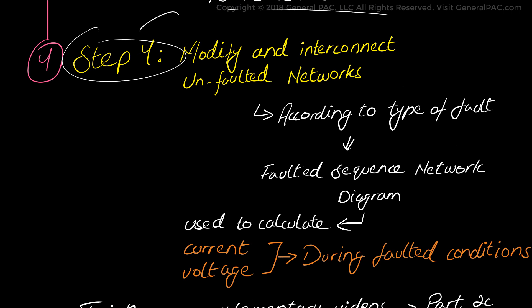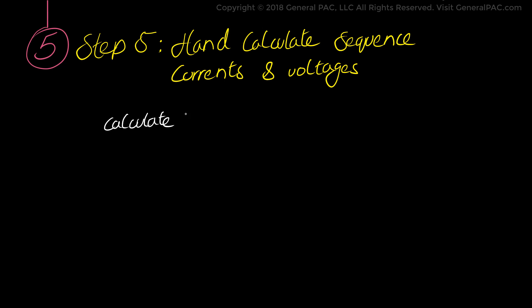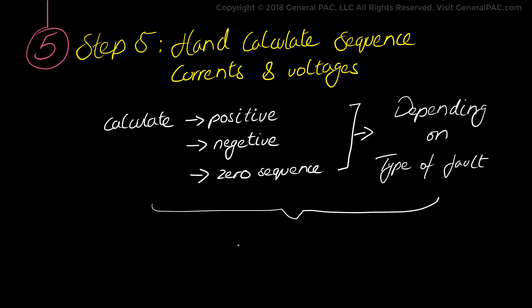Now in step number 5, we will hand calculate the sequence current and voltage quantities during a faulted condition. So we will calculate the positive sequence current, the negative sequence current and the zero sequence current, depending on the type of fault that is involved. And keep in mind that step 5, these current and voltage quantities are per unit values.